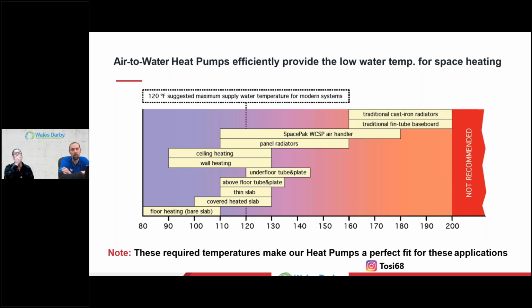In the five boroughs of New York City, there are requirements now with this new R32 that most manufacturers are going with, where you can't have more than 4 pounds, 4 ounces of refrigerant in a space larger than, I think, 1,000 cubic feet. So it's a 10 by 10 room with 10-foot ceilings. It's a small little room. If there's more than 4.4 pounds of refrigerant that can get into that space, then you can't have it.